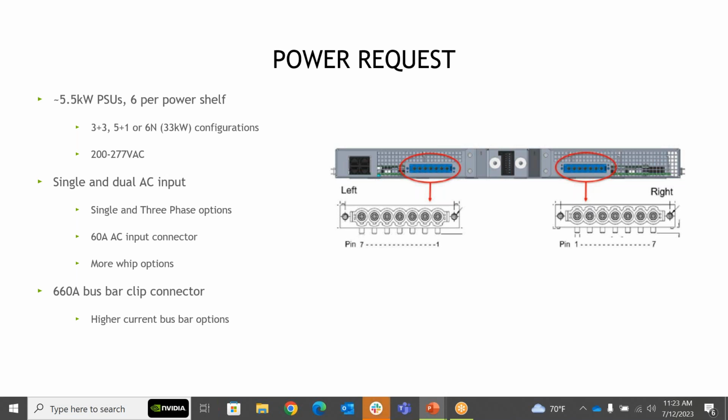Honestly, as we go to a 60 kilowatt or higher rack, with 208, lower current feeds, the power whips and the power shelves, the counts that you need become, it's possible, but when you have just as many power shelves as you do compute trays, I think our part of the industry can do better and increase our density, because more GPUs is the direction, and looking at how we can enable that from a power perspective. Yep, that's a good point.